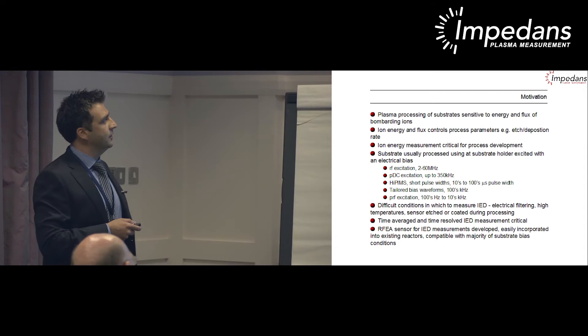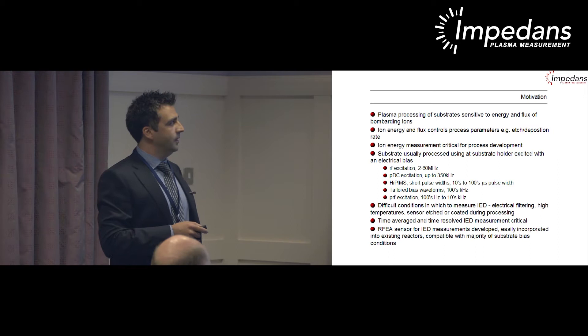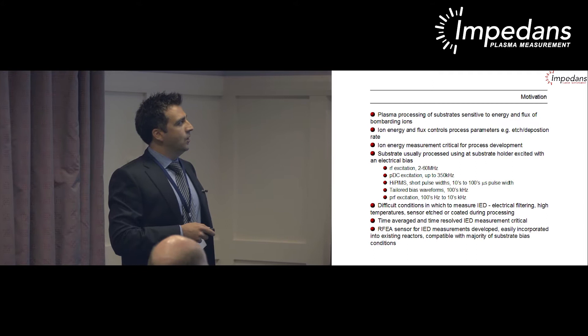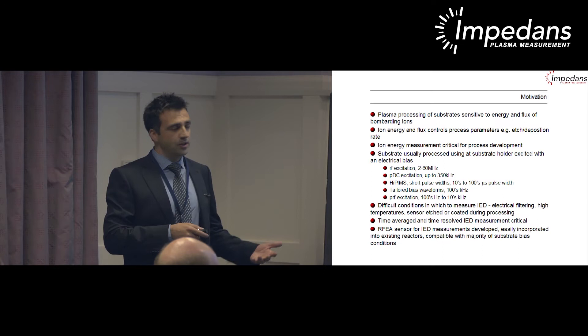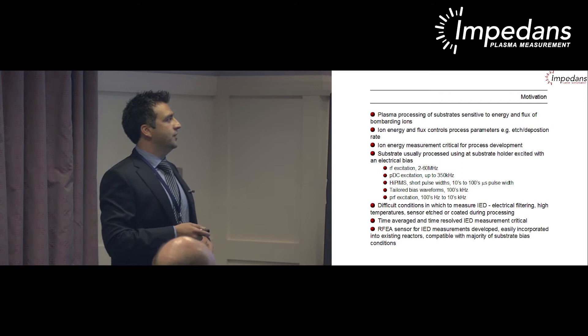Other bias types include HiPIMS with very short pulses of tens to hundreds of microseconds, tailored bias waveforms for more control over bombarding ion energy, and pulsed RF applications typically pulsed in the hundreds of hertz to tens of kilohertz range with an RF component on top. These are quite difficult conditions for measuring ion energy distribution. One must think about electrical filtering of the bias signal, high temperatures in the discharge, and sensor lifetime—it may be etched away or coated during processing.